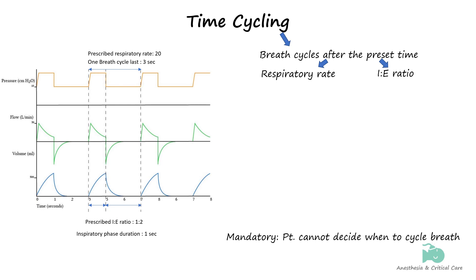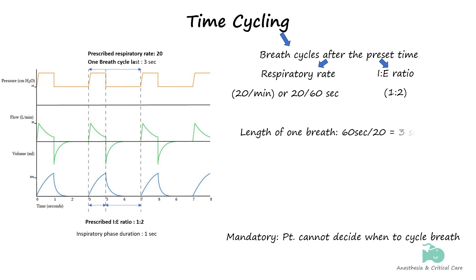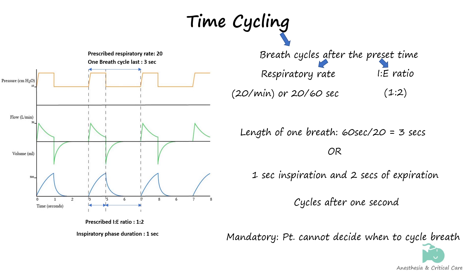For instance, when one has a respiratory rate of 20 and an inspiratory-to-expiratory ratio of 1:2, it is understood that from a total 3-second breath cycle, the inspiratory phase will last 1 second. In other words, after 1 second the ventilator will terminate inspiratory flow and cycle to expiration.